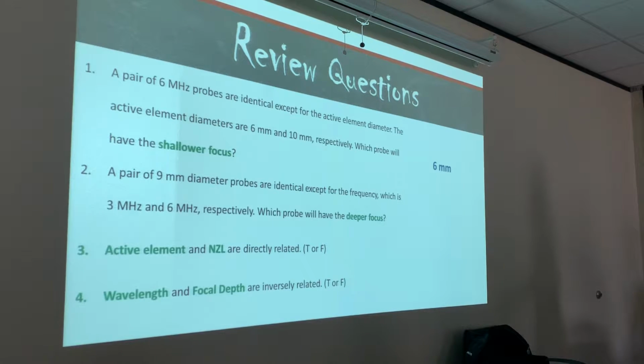Number 2, guys, a pair of 9 millimeter probes are identical except for the frequency, which is 3 megahertz and 6 megahertz. Which probe will have the deeper focus? 6. Our higher frequency transducer is going to have the deeper focus because the focal depth and frequency are directly related. So our 6 megahertz transducer is going to provide us with the deeper focus.